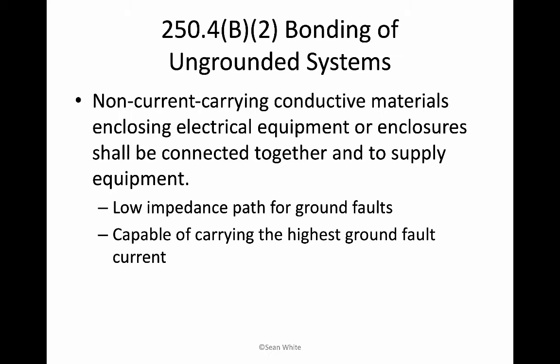One of the things that you might have to look out for is if you have a system that you're connecting to. Let's say that the existing building has 277/480. You can hook up a 480 delta ungrounded inverter to that, but you cannot do the other way around. So if you had a 480 delta building, you can't connect a 277/480 inverter to that, because all of a sudden you would be grounding the building through your inverter, which ain't going to happen. That would be a bad thing to do. And that's kind of a common thing that people run into. So just remember, if you had an ungrounded delta inverter, you could connect to a grounded building or outdoor system.